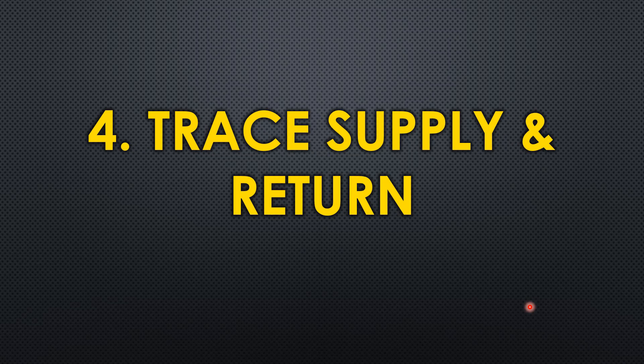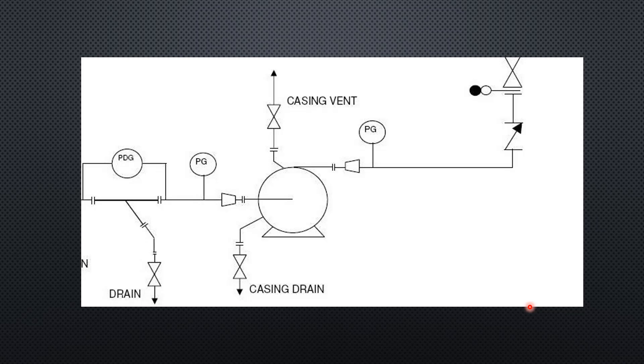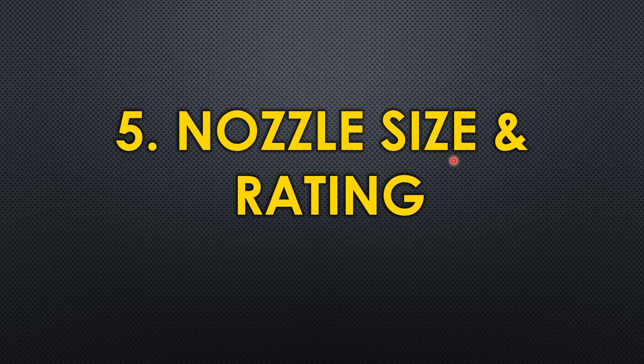The fourth parameter is tracing the supply and return of the piping — where it comes from and where it goes. You must understand this because only then can you plan the correct location for the pump. The distance from the supply source to the pump should be as short as possible for the pump to work efficiently. That is why tracing supply and discharge locations is essential.